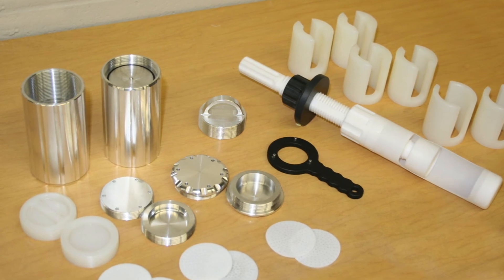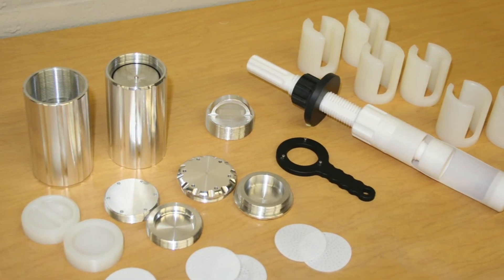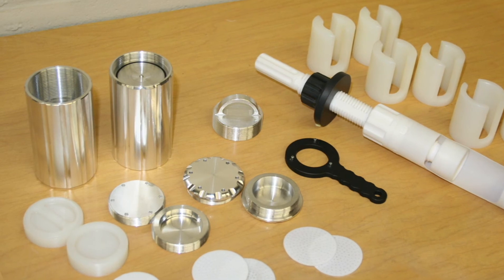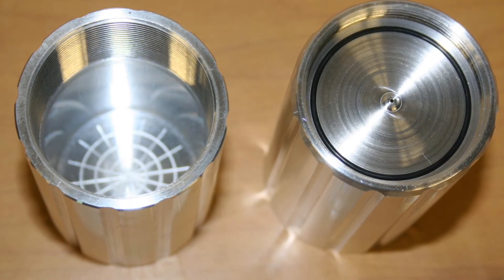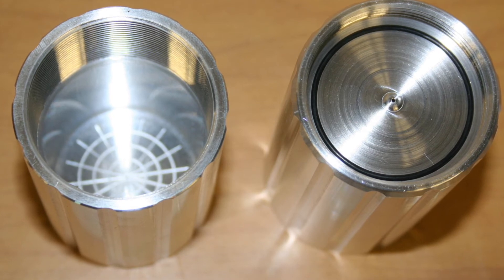Special centrifuge cups are available that ensure expelled fluid does not re-enter the core. They are not transparent and have no graduations as there is no need to measure the expelled fluid.